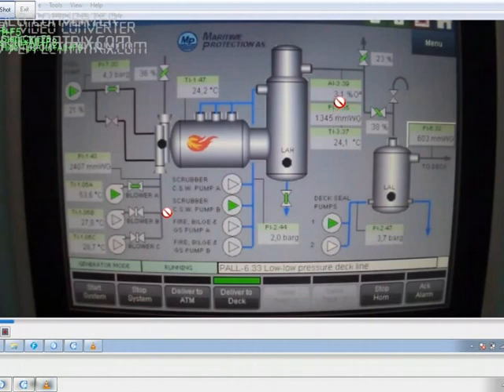You can see here right now the oxygen is 3.1%. Temperature here is 24.1. The pressure is 1345 mm WG here. You can see the valve throttle 38%.